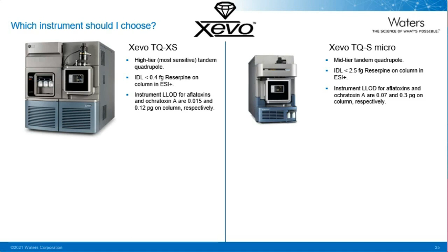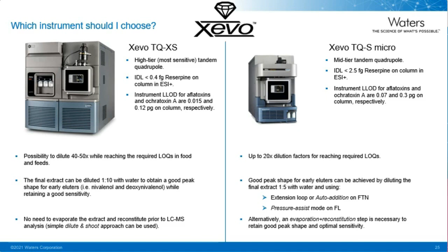This means that on the TQ-XS we can dilute the final extract 1 in 10 with water and get good peak shapes while retaining a good sensitivity. On the other hand, on the Micro, we can dilute with water up to 5 times, but we need to find alternative ways to obtain good peak shapes for early eluters. Alternatively, an evaporation and reconstitution step is necessary.